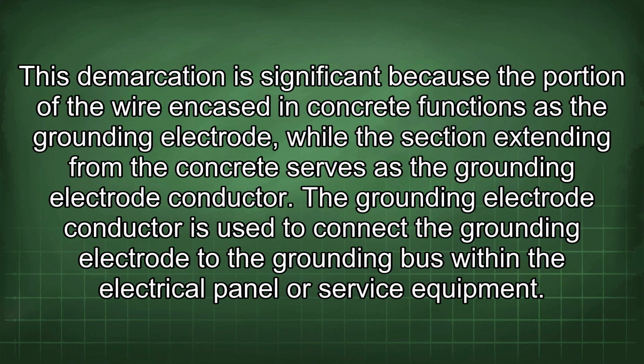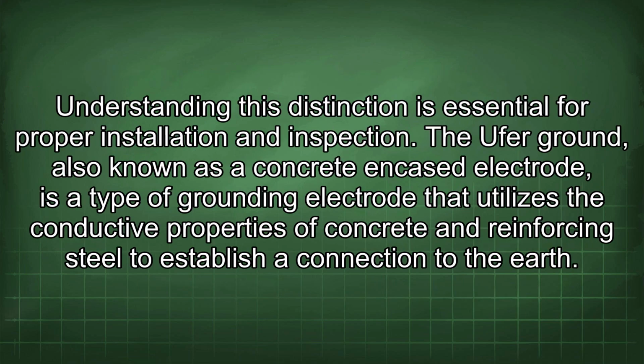This demarcation is significant because the portion of the wire encased in concrete functions as the grounding electrode, while the section extending from the concrete serves as the grounding electrode conductor. The grounding electrode conductor is used to connect the grounding electrode to the grounding bus within the electrical panel or service equipment. Understanding this distinction is essential for proper installation and inspection.